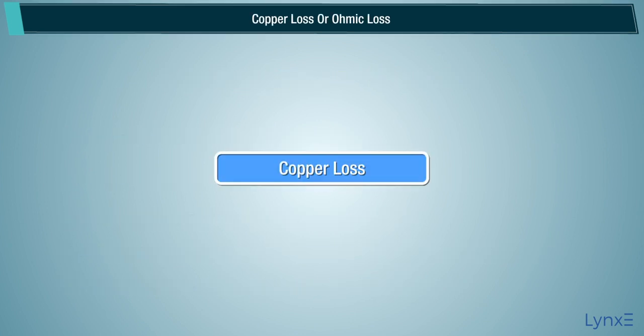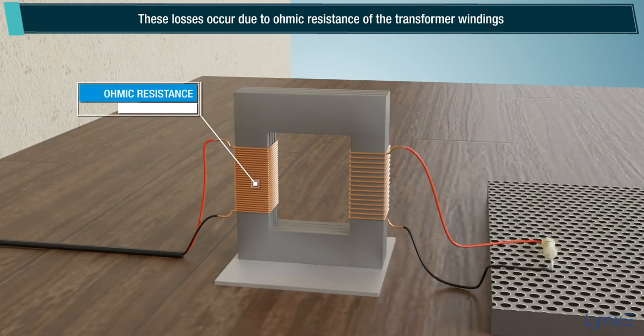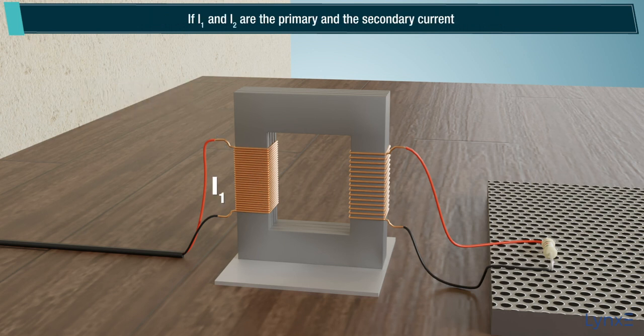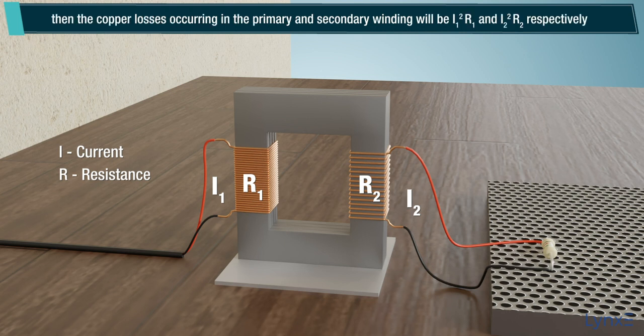Copper loss or ohmic loss. These losses occur due to ohmic resistance of the transformer windings. If I1 and I2 are the primary and the secondary current, R1 and R2 are the resistance of primary and secondary winding, then the copper losses occurring in the primary and secondary winding will be I1 square into R1 and I2 square into R2 respectively.